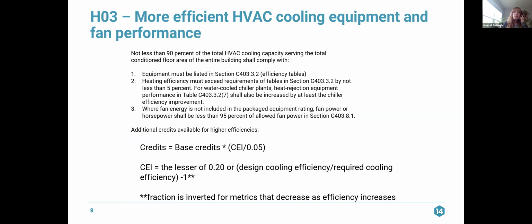The next credit, H03, is very similar, except for its cooling. And then you also have to look at fans with this credit. So this one is a little bit funky. So it's similar, but it's a little funky. Same requirement around 90% of the total HVAC cooling capacity serving the total conditioned floor area of the entire building shall comply with these sections. So the equipment must be listed again in that section C403.3.2. We have to know what we're comparing it against. But again, it's hard pressed to come up with a system that isn't included in the tables in section C403.